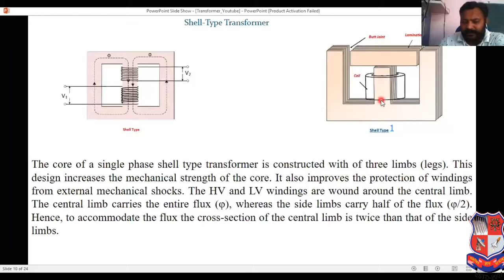The HV and LV windings are wound around the center limb. The center limb carries the entire flux phi, whereas the side limbs carry half of the flux, phi by 2. These are your side limbs. This is your main limb, on which your LV and HV are mounted. Hence, to accommodate the flux, the cross section of the center limb is twice that of the side limbs. So by default, when two windings are mounted on the center limb, the cross section of the center limb will be more than that of the others.